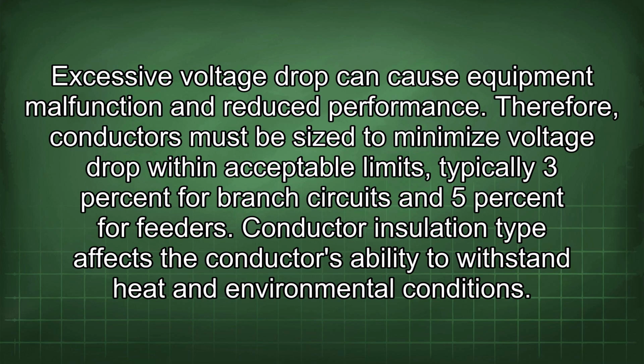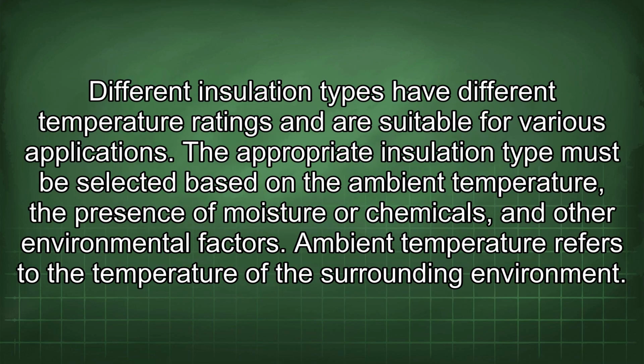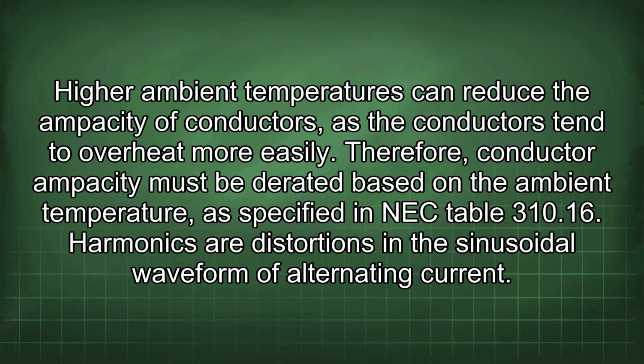Conductor insulation type affects the conductor's ability to withstand heat and environmental conditions. Different insulation types have different temperature ratings and are suitable for various applications. The appropriate insulation type must be selected based on the ambient temperature, the presence of moisture or chemicals, and other environmental factors. Ambient temperature refers to the temperature of the surrounding environment. High ambient temperatures can reduce the ampacity of conductors, as the conductors tend to overheat more easily. Therefore, conductor ampacity must be derated based on the ambient temperature, as specified in NEC Table 310.16.